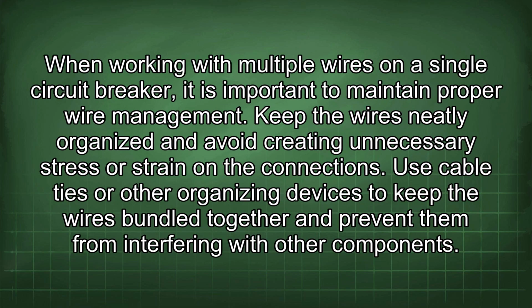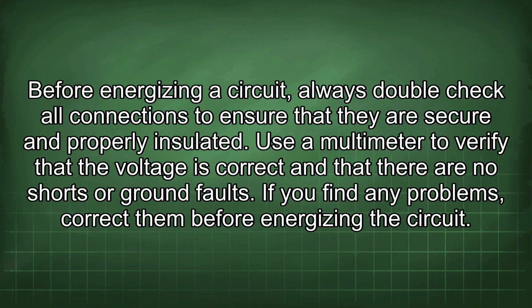When working with multiple wires on a single circuit breaker, it is important to maintain proper wire management. Keep the wires neatly organized and avoid creating unnecessary stress or strain on the connections. Use cable ties or other organizing devices to keep the wires bundled together and prevent them from interfering with other components. Before energizing a circuit, always double-check all connections to ensure that they are secure and properly insulated. Use a multimeter to verify that the voltage is correct and that there are no shorts or ground faults. If you find any problems, correct them before energizing the circuit.